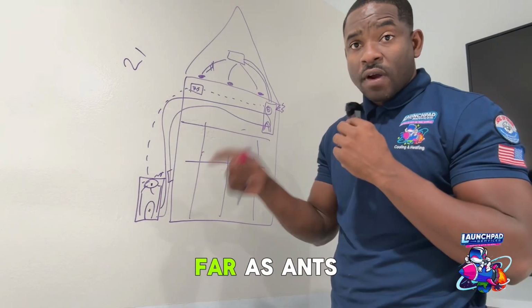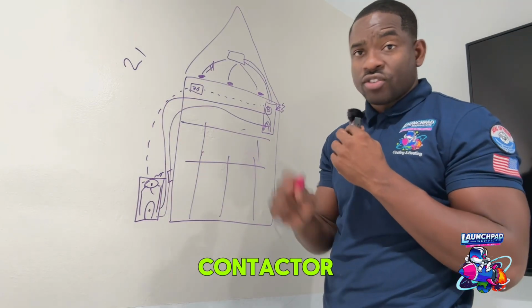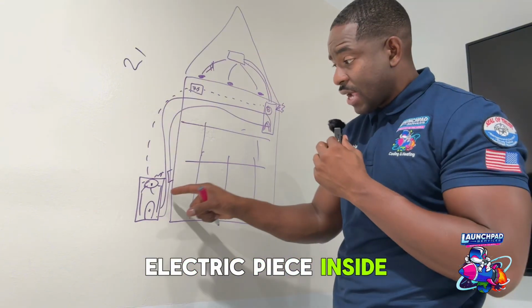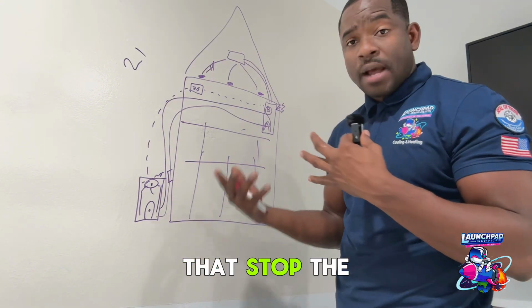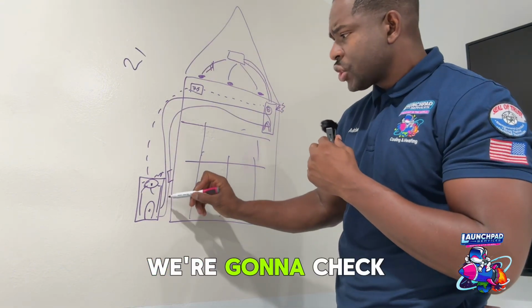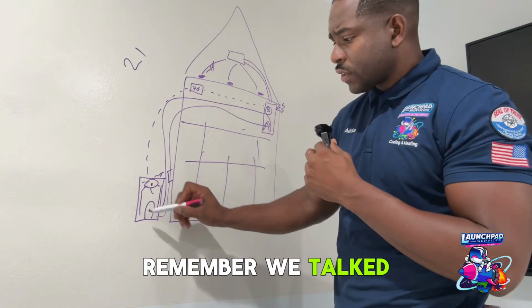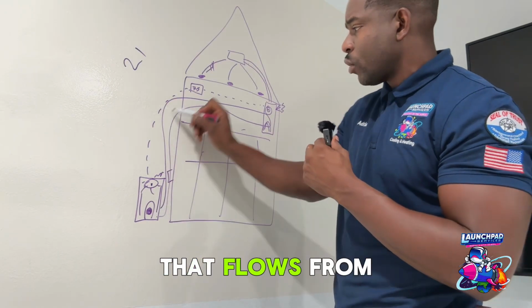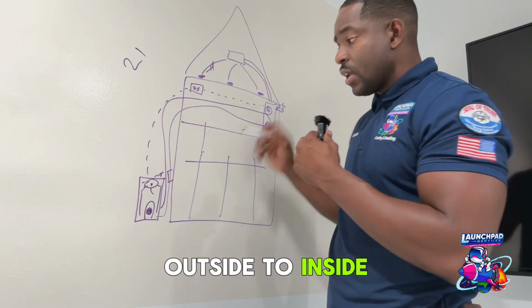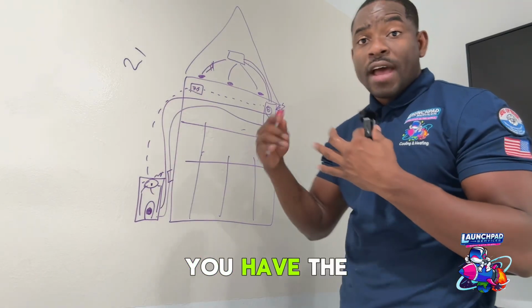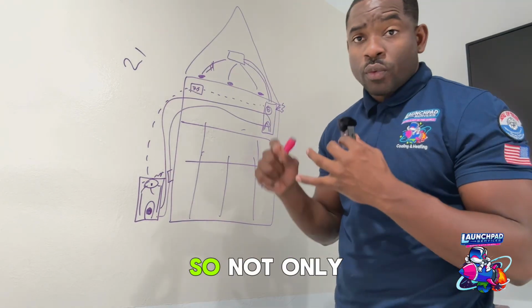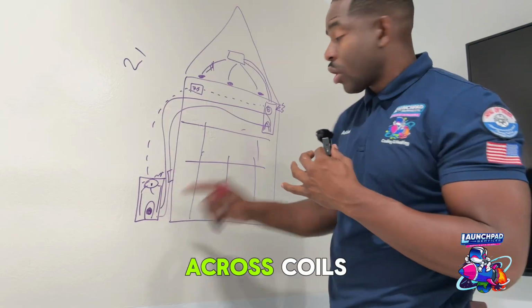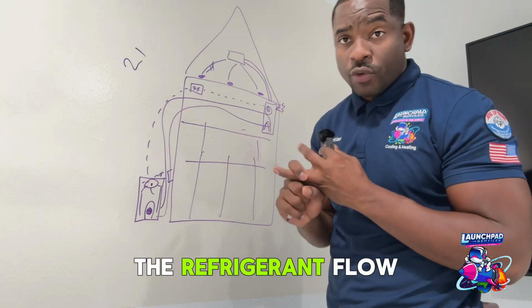I've seen as far as ants filling up a contactor, which is an electric piece inside your air conditioner, that stopped the system from running. We're going to check refrigerant pressure. Remember we talked about that juice that's in the system that flows from outside to inside? Well, we got to make sure you have the right amount of refrigerant. So not only are we going to check airflow across coils, we're going to check the refrigerant flow.